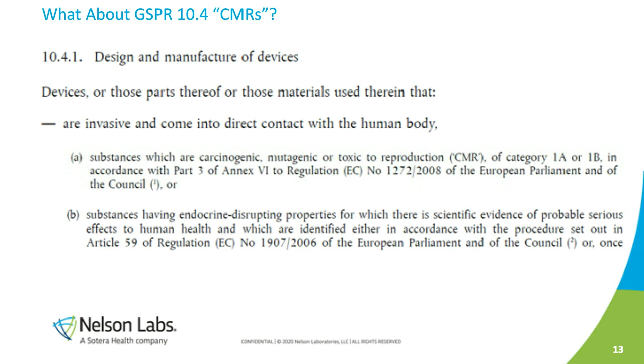So GSPR 10.4 in the MDR specifies that devices or parts thereof or those materials therein, so the materials that make up a medical device, really should be free of these substances which are carcinogenic, mutagenic, or reproductive toxicants. So that's CMRs. And in addition to that, they should be free of these endocrine disruptors. There's some code there that refers directly to chemical lists that you can go online and download in Excel format. So this one, Part 3 of Annex 6 to Regulation 1272, that's the CLP Annex in the EU. And if you download that, you can download an Excel file and filter, so you just view the CMRs, right?